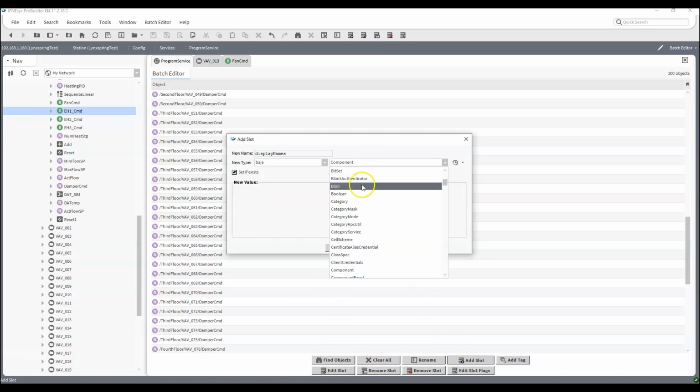Now, some things it won't let you do. Like if the syntax is off, it's not going to go through. So that one is always good. That's kind of like the catch-all there. So again, let's go back to override equals override damper position, semicolon, auto equals release damper override. And you still need a semicolon, regardless.